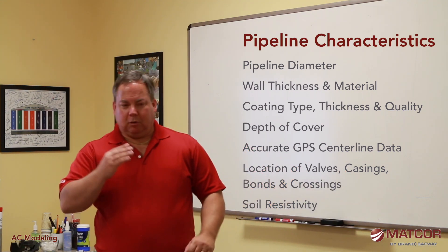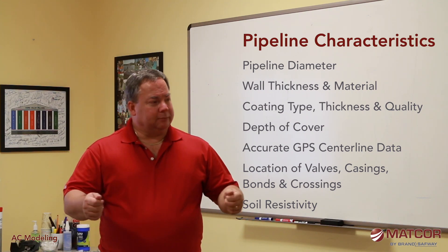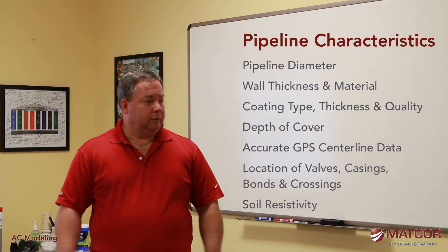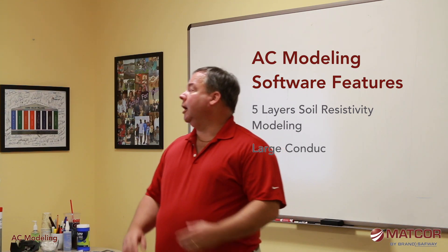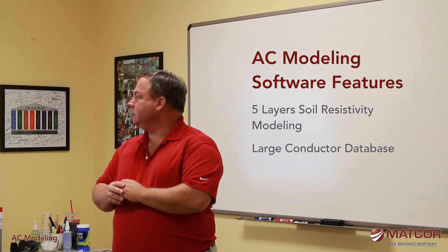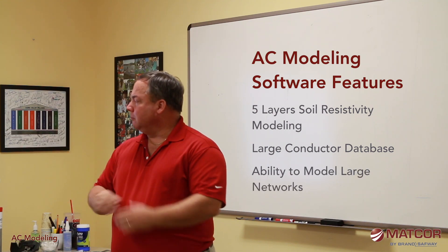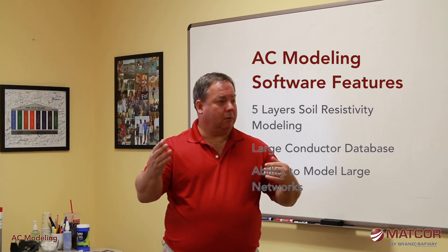We need a good picture of soil resistivity at different depths — 2-foot, 5-foot, 10-foot, and even 100-foot depth — at multiple locations along the pipeline. The SES software has the ability to model multi-layer soil effects up to five or more layers. We have a large conductor database including most transmission line conductors, all copper conductors, and mitigation devices like zinc ribbon. The software can model large networks including multiple power lines and multiple pipelines in the same corridor.